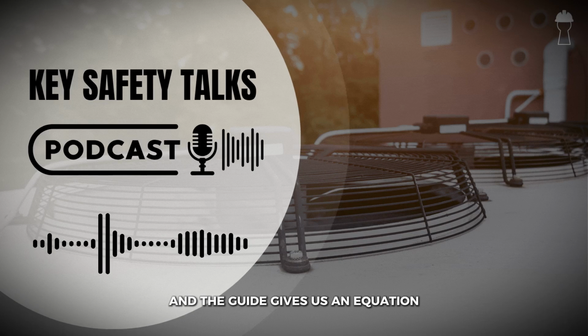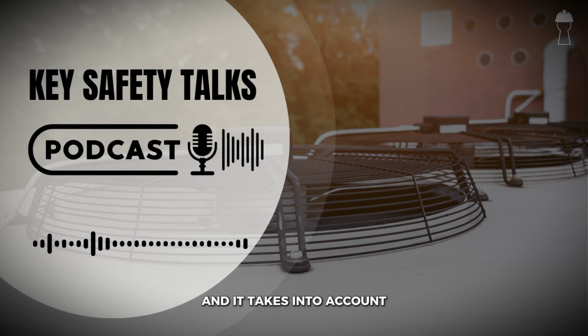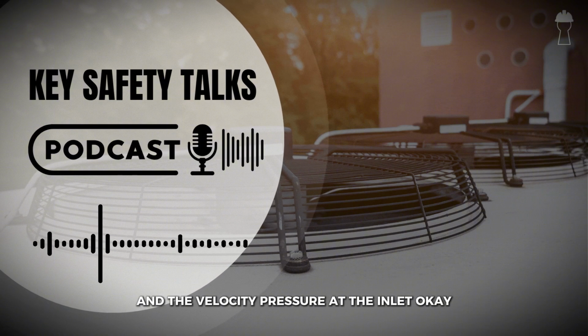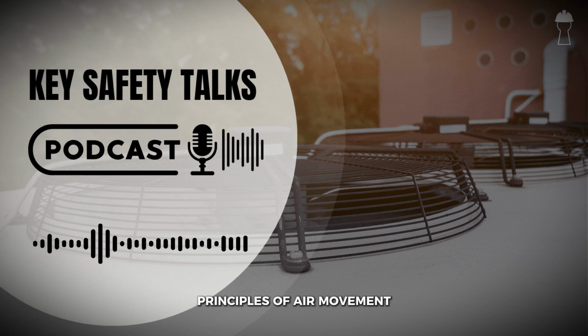Right. And the guide gives us an equation for calculating the static pressure, and it takes into account the static pressure at the outlet and the velocity pressure at the inlet. Okay, so it all comes back to those basic principles of air movement we talked about before.